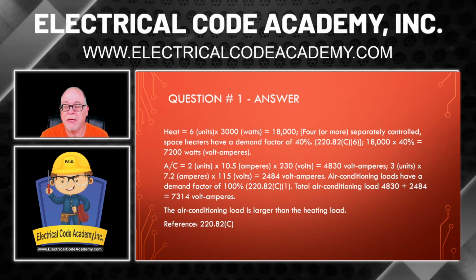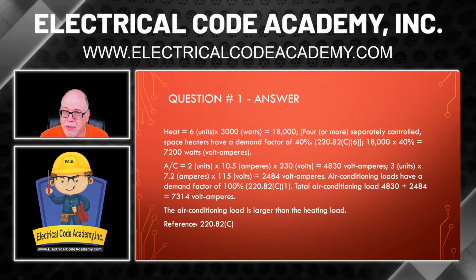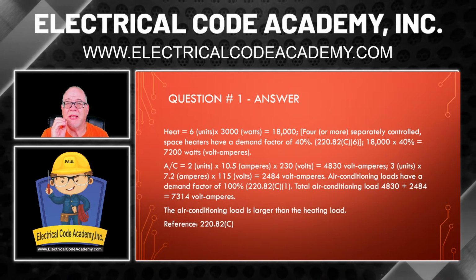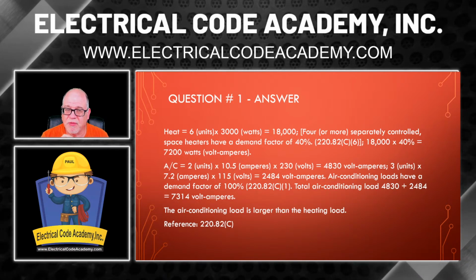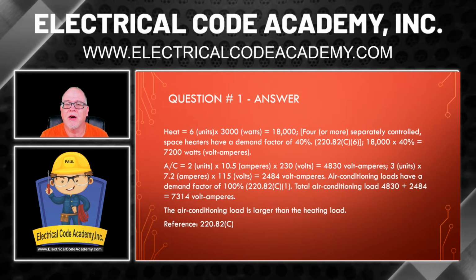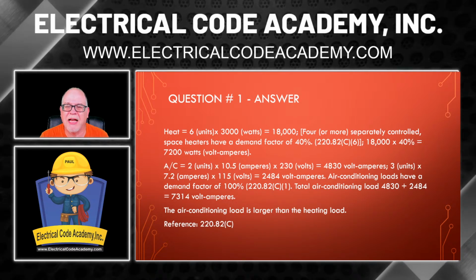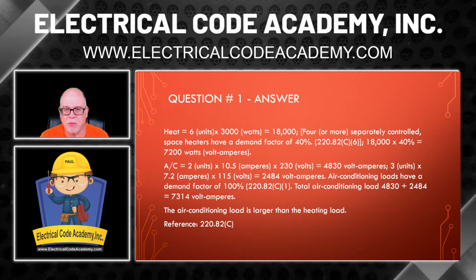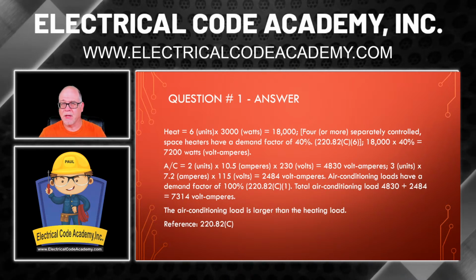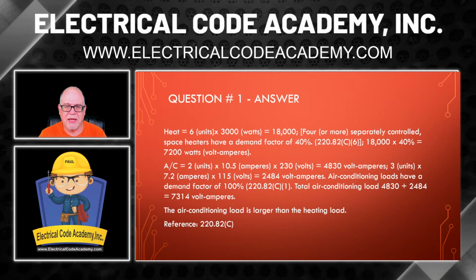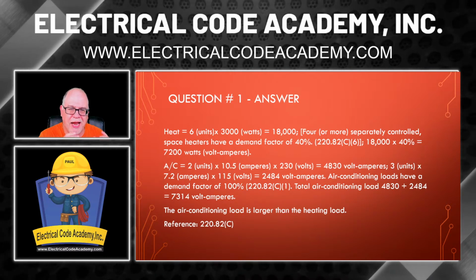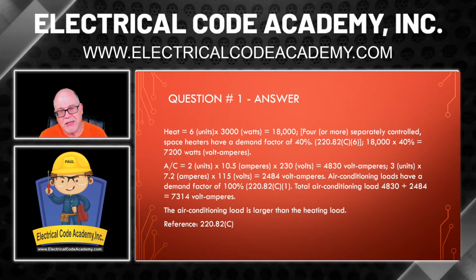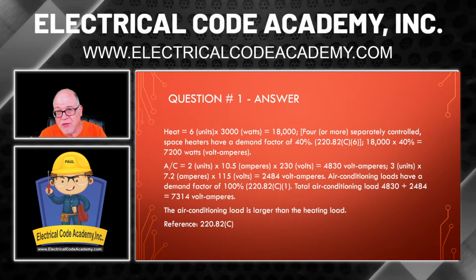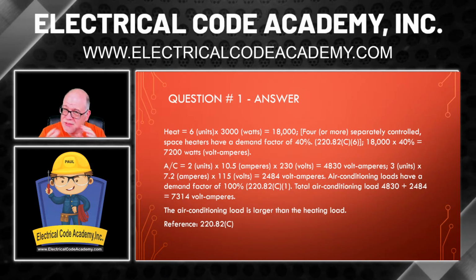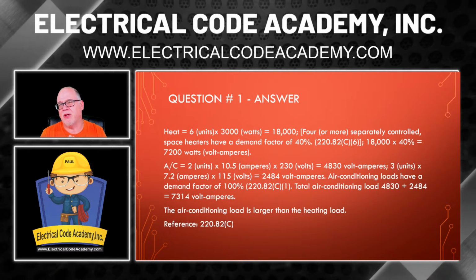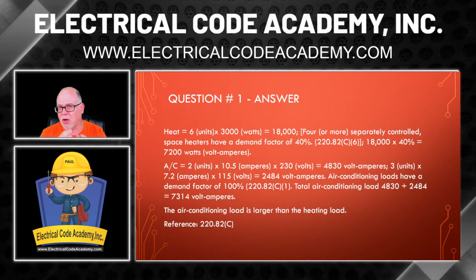Now let's do the 3 7.2 amp air conditioning units. That would be 3 times 7.2 times 115 volts. That is 2,484 volt-amperes. Remember Ohm's law: in order to find VA, it's synonymous. We're just going amps times volts equals watts, and watts is synonymous with VA. See how that works?